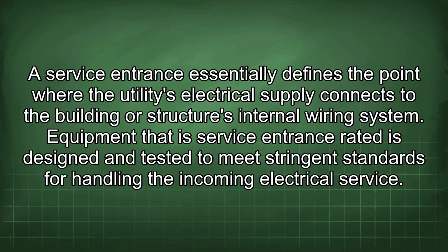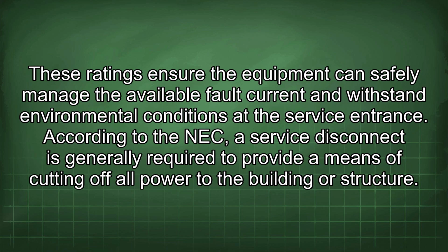A service entrance essentially defines the point where the utility's electrical supply connects to the building or structure's internal wiring system. Equipment that is service entrance rated is designed and tested to meet stringent standards for handling the incoming electrical service.